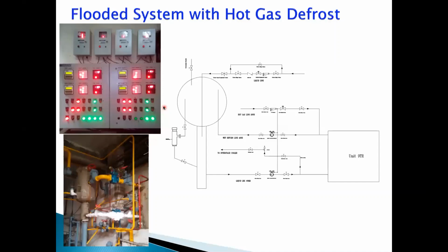So what we have to do is remove that frost. The less frost we maintain, the more efficient the system. That's why I was talking right from the initial stage about defrosting. We need to remove this frost. It's called defrosting, and defrosting can be done in different ways. The most popular, and the oldest, was defrosting a coil by using air defrost. Air defrost means you shut off the plant and maybe keep the door open for a few hours, and because of the increase in room temperature, the coil defrosts.